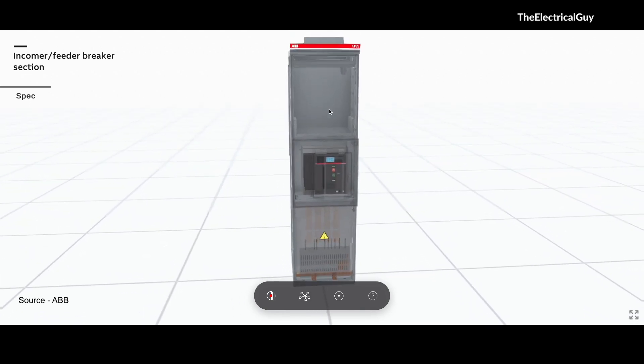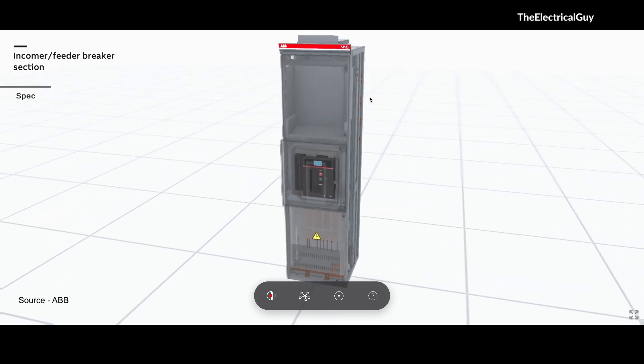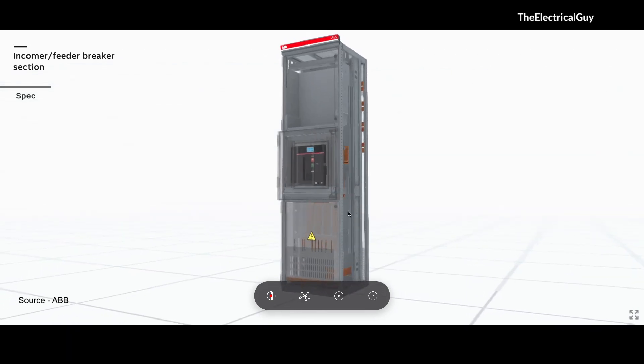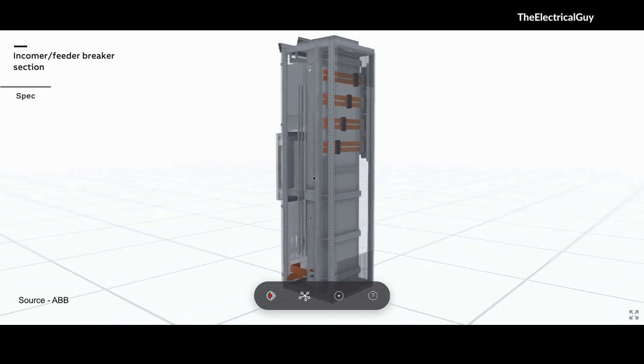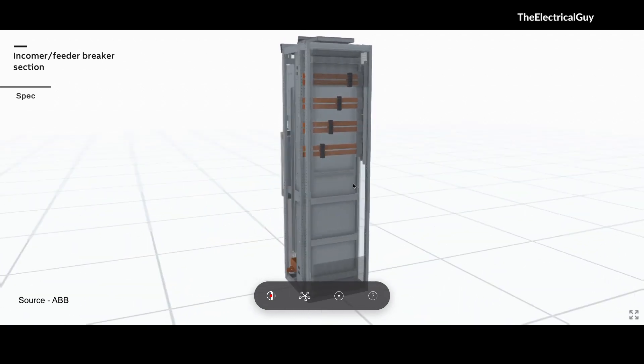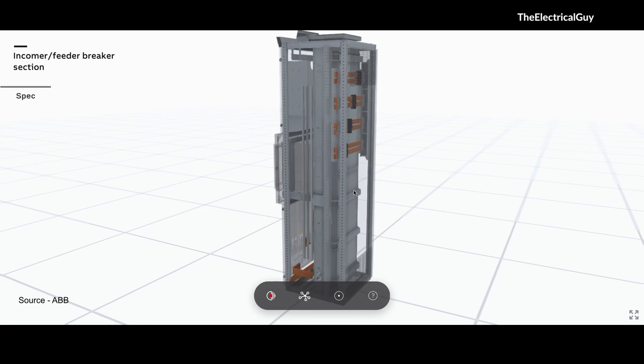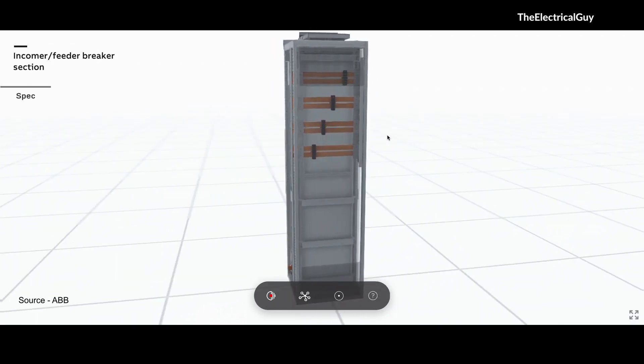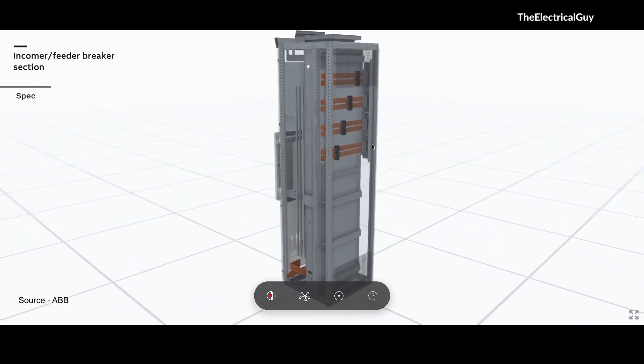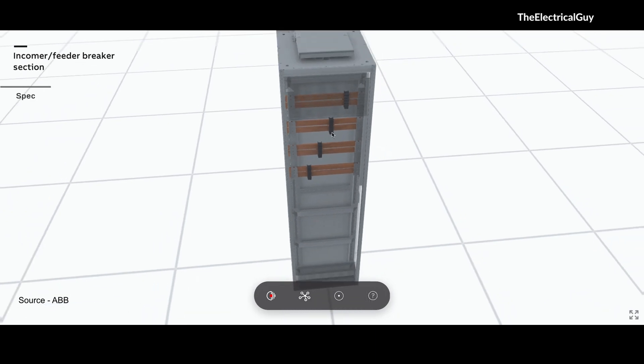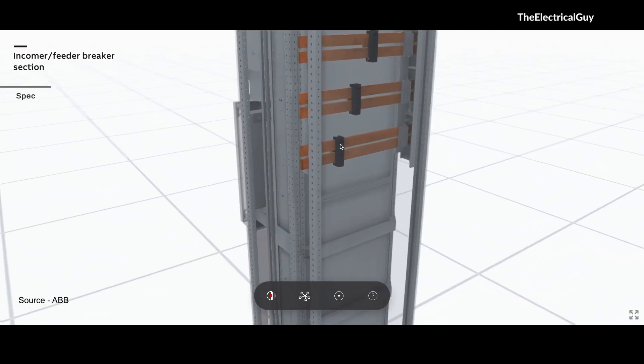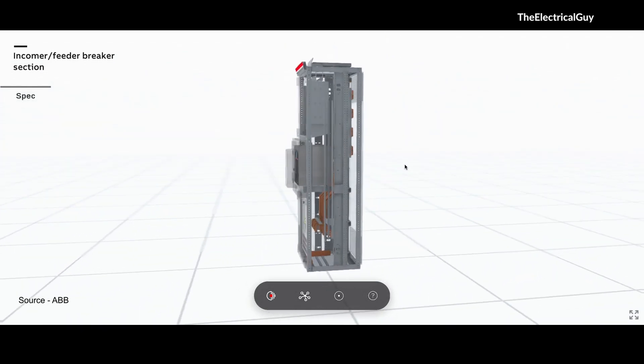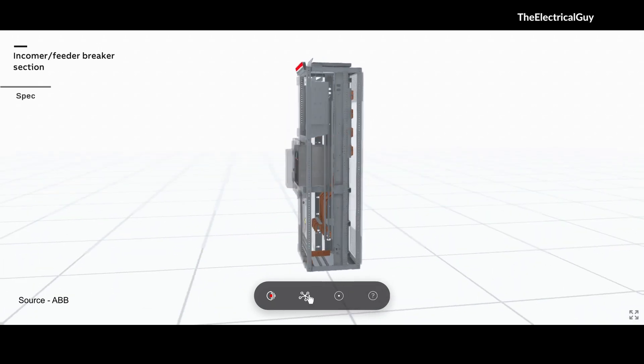On the top of the panel there is some blank space where we can mount auxiliary equipment — MCBs, surge protecting devices, control devices, and similar things. At the back side we have the main bus bars. This design is called the rear side bus bar design. We have different options: top bus bar, bottom bus bar, front or rear side. The rear arrangement offers certain advantages. You can see the copper bus bars here with R, Y, B and neutral. The black portion you see is the current transformer used to measure current, and it also supports the bus bar.